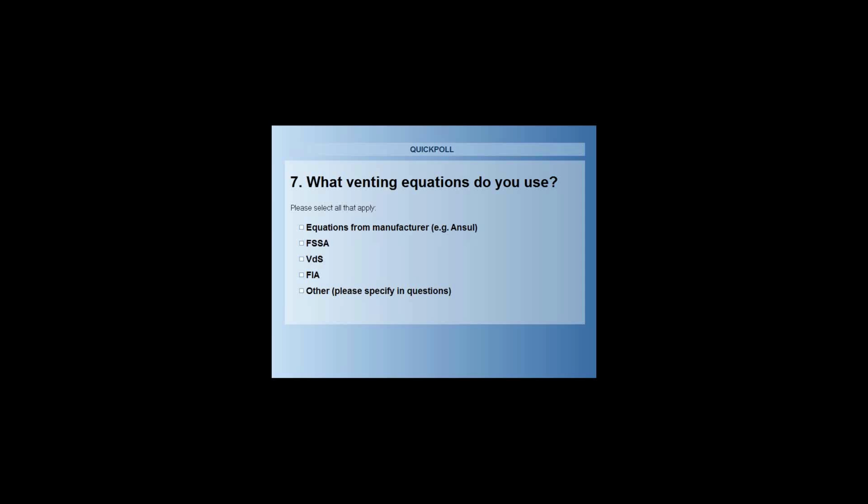Zachary is asking, the equations are built into the flow calculation software. Oh, okay. So Zachary's saying that the peak pressure calculations are built into their software. So I guess we take issue with them and don't think they're correct in a lot of cases. Incidentally, it was the clean agent manufacturers themselves that sponsored the peak pressure evaluation project that was done at FICO over a 4 or 5 year period, and it was by far the most comprehensive and open process. As many as 4 or 5 different manufacturers, all the major manufacturers, were involved on some level, and most of them attended at least one of our sessions, if not all of them. So it wasn't something that was done in secret, and all this information has become public knowledge.